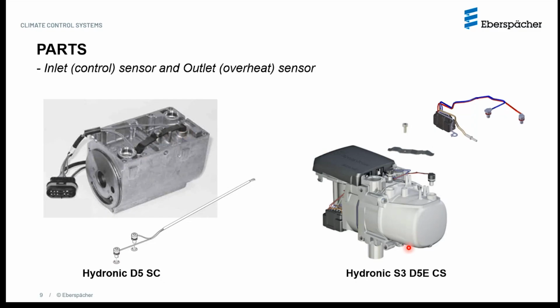For the Hydronic third generation heater, it's a very similar concept. You do have the two sensors, the overheat sensor and the control sensor, but in the documentation they are not referred to as such. They are referred to as the inlet sensor and the outlet sensor. So with the third generation, the terminology slightly changes, but even though the verbiage changes, the function does not. The sensor attached to the red harness is still measuring overheat, whereas the sensor attached to the blue part of the harness is monitoring the temperature of the coolant, based on which your heater operation is decided.